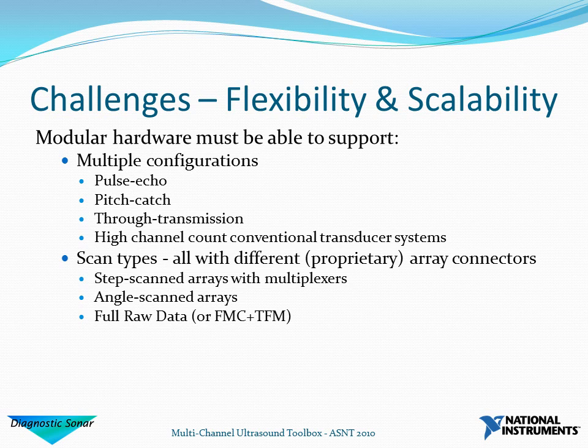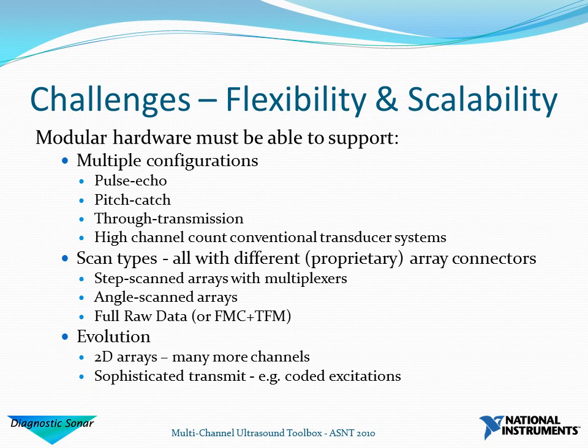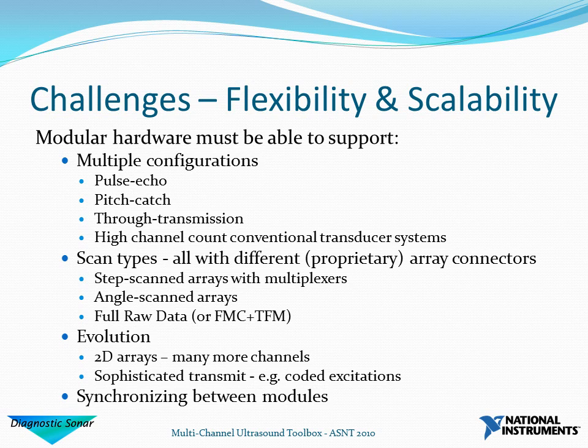We've already discussed step-scanned arrays with multiplexing. Without a multiplexer, you can use almost the whole aperture on transmit and receive for every beam, scanning through angles by providing a skewed delay profile. We also need to be capable of addressing full raw data systems. Looking to the future, there's going to be a migration towards two-dimensional arrays involving many more channels, even with sparse arrays. We also want to handle sophisticated transmits such as coded excitations, and where we need multiple modules, we need very tight synchronization between them.